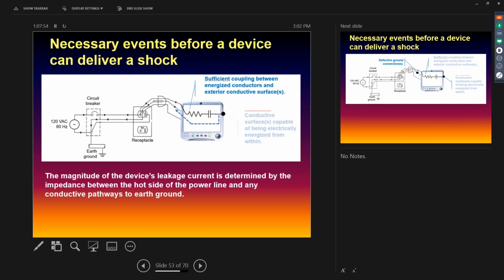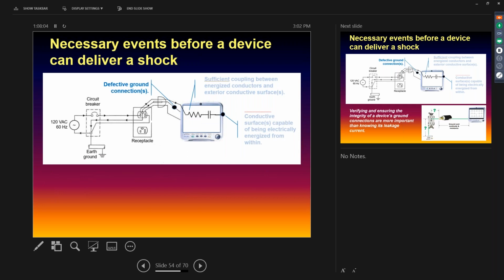Third thing, and again it's that impedance here that determines that coupling. Third thing we have to have is a defective ground, either from the case to the plug, from the plug to the outlet to physical earth, a defective ground. If we've got an intact ground, frankly we don't care what the leakage current is.